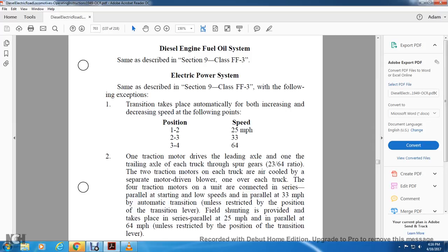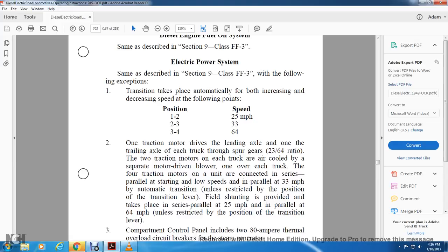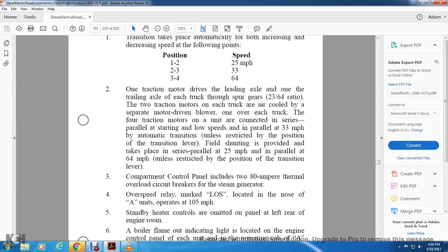Either truck is air cooled by a separate motor driven power blower, one over each of the trucks. The 4 traction motors on a unit are connected in series parallel, starting at low speed, with the parallel at 33 miles an hour automatic transition unless restricted by the position of the transition lever. Field shunting is provided, taking place in series parallel at 25 miles an hour and parallel at 64 miles an hour, unless restricted by the position of the transition lever. The compartment of the control panel includes the two 80-ampere thermal overload circuit breakers, the steam generator overspeed relay located in the nose of the A units, operated at 105 miles per hour, and the standby heater control.